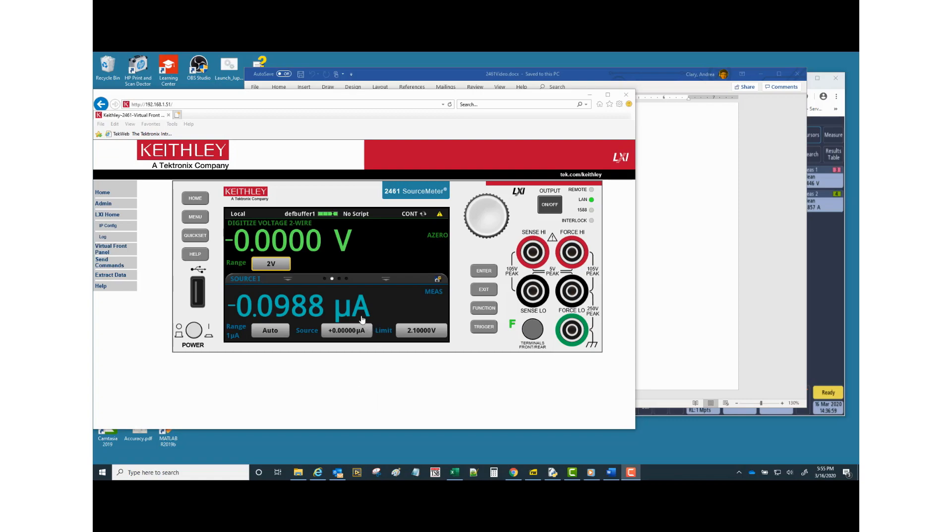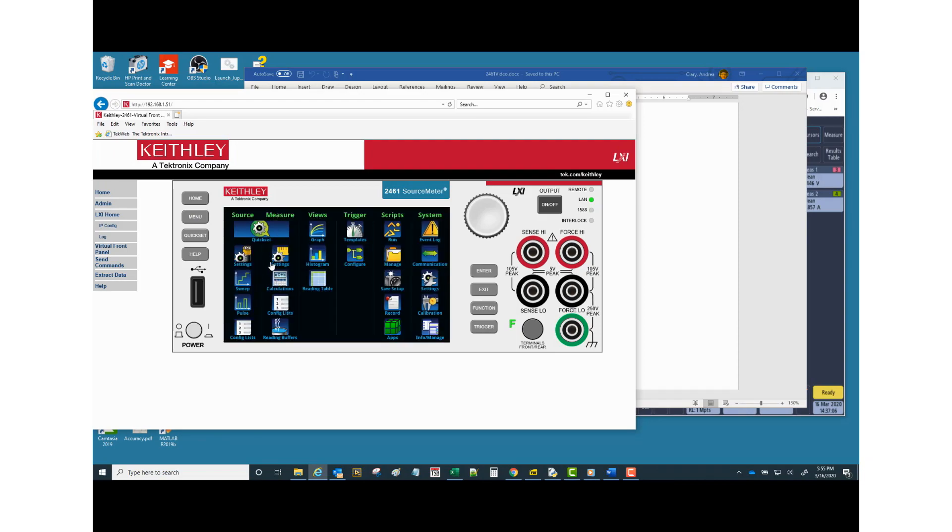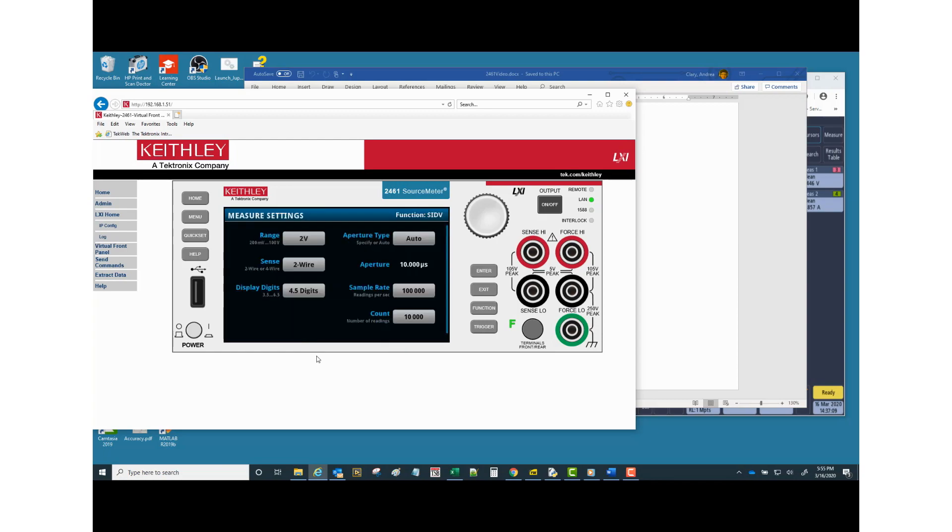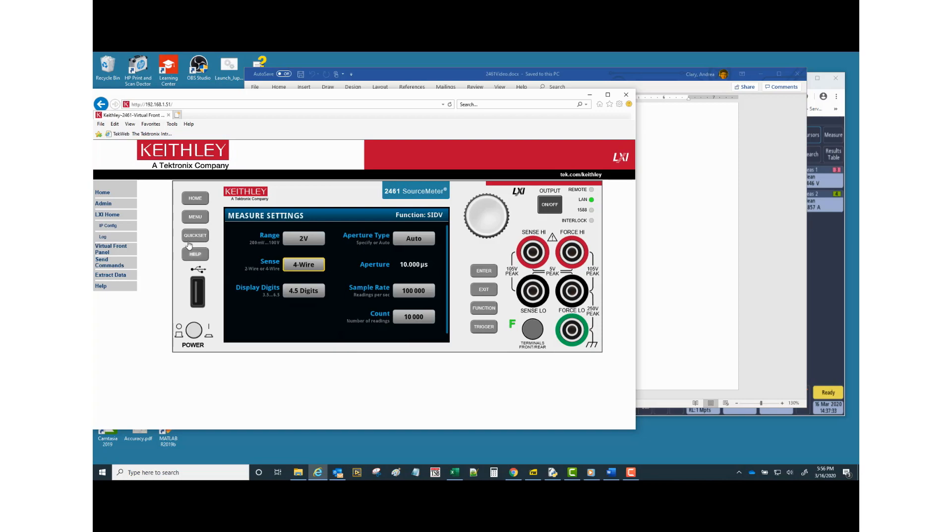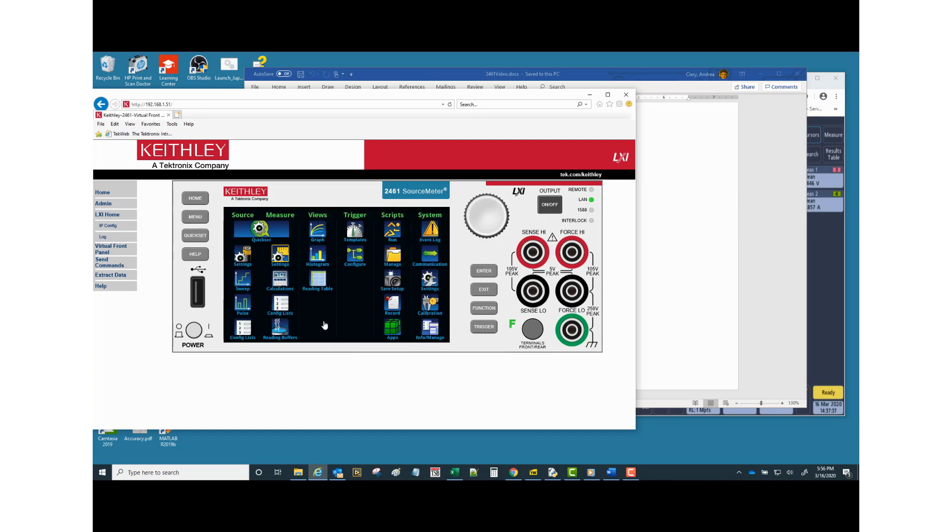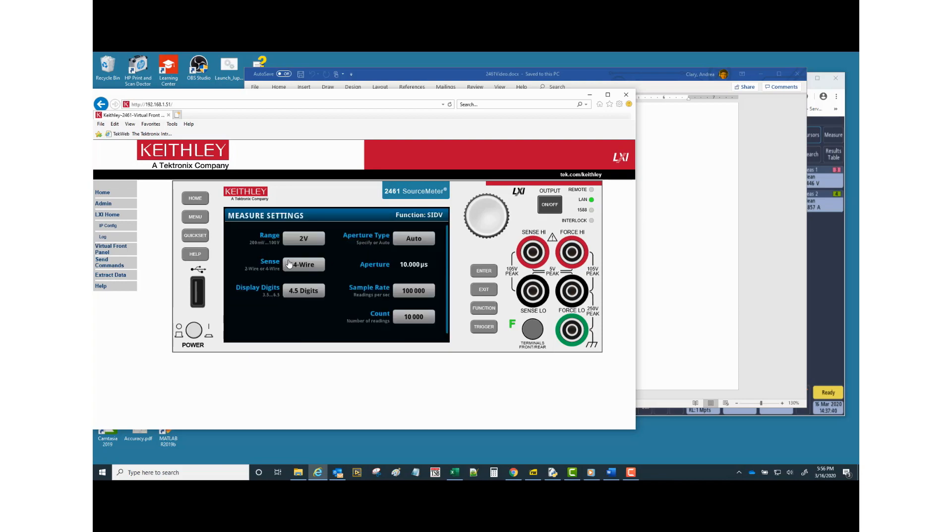So now in order to set up the pulse, we've got to make a couple other changes. So under the measure, I'm going to come into the settings, and I want to set this to the four wire sensing. So I have connected the remote sense lines, but now I need to configure the instrument to utilize them. In the previous step, when under the quick set, when we said source current and digitize voltage, then that brought into effect settings appropriate for that digitizer. And for now, let's just accept the defaults. I'm going to press the menu button. So the only thing I changed under measure was the four wire mode.